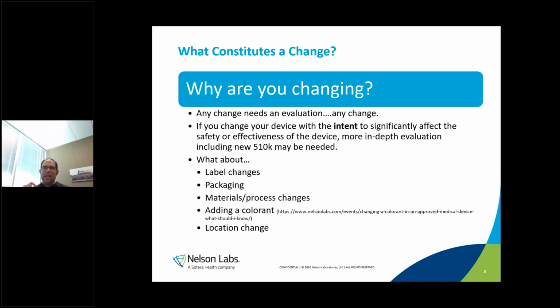And I do want to say that any change to a medical device, be it the packaging, the sterilization procedure, the processing, the additives into the polymers, anything that's being changed should go through a biocompatibility evaluation. That doesn't mean you have to repeat testing on any change. That's not what I'm saying. I'm saying the evaluation needs to be done.